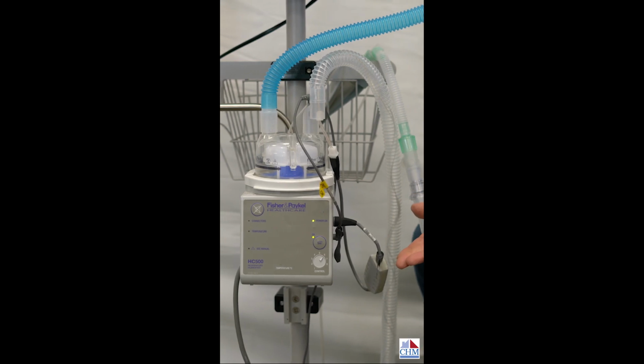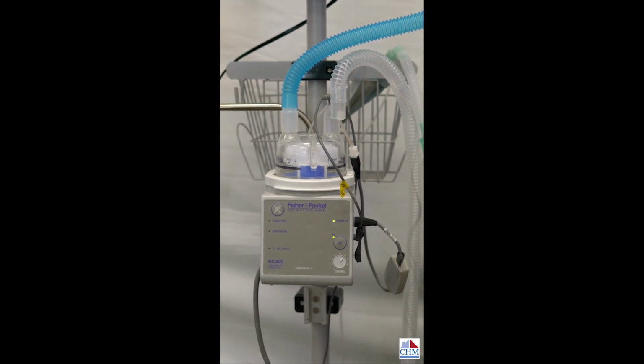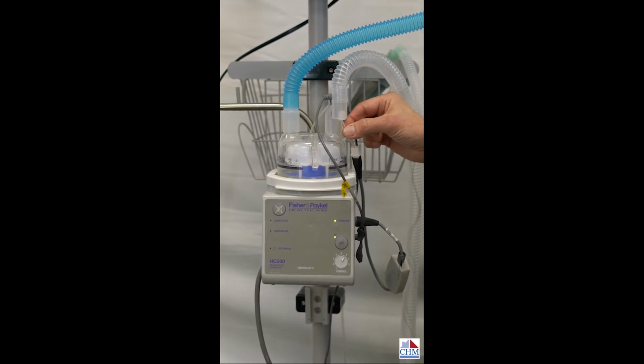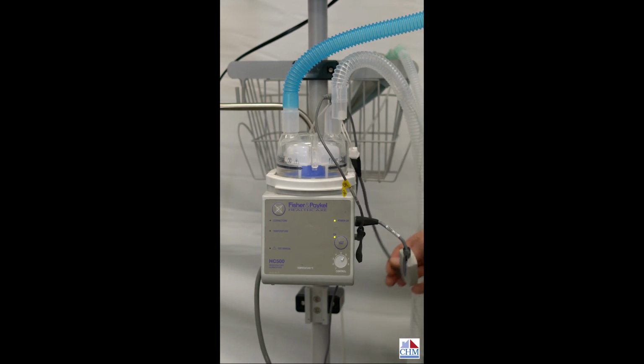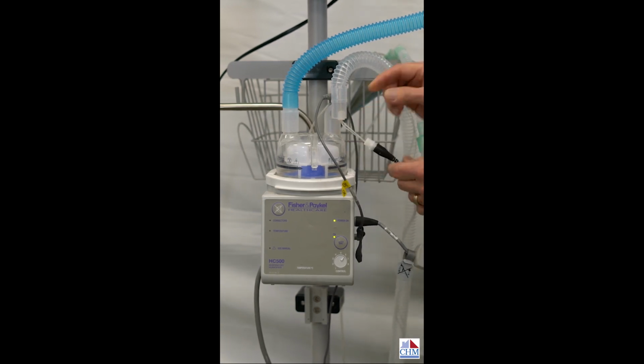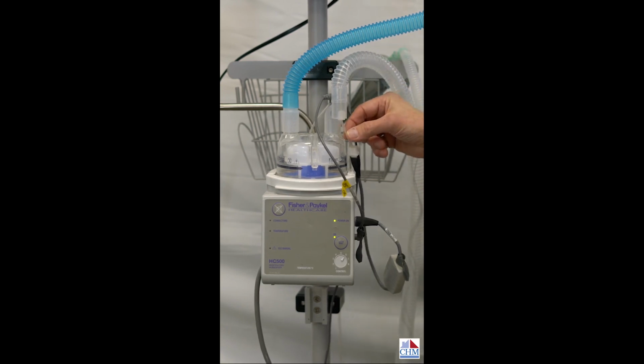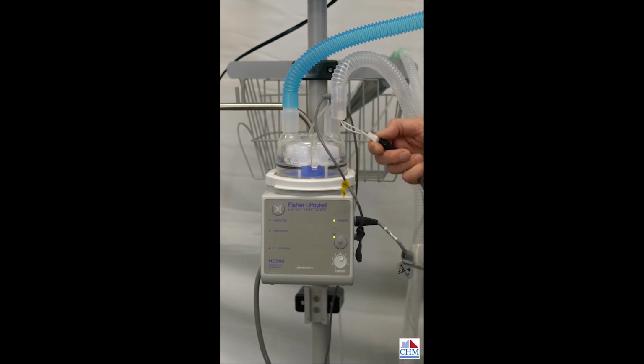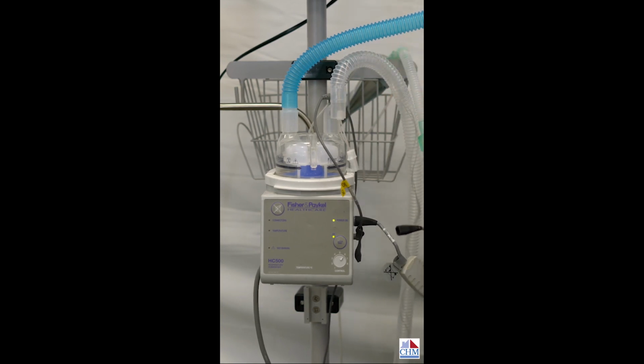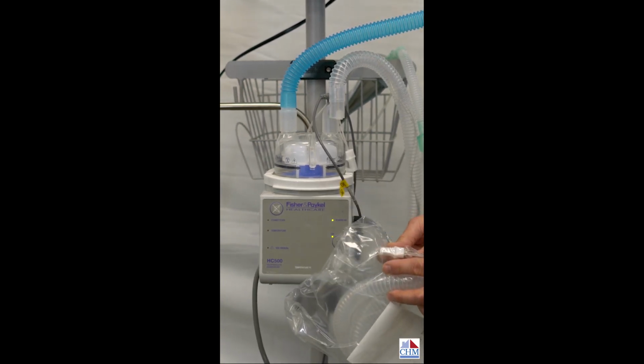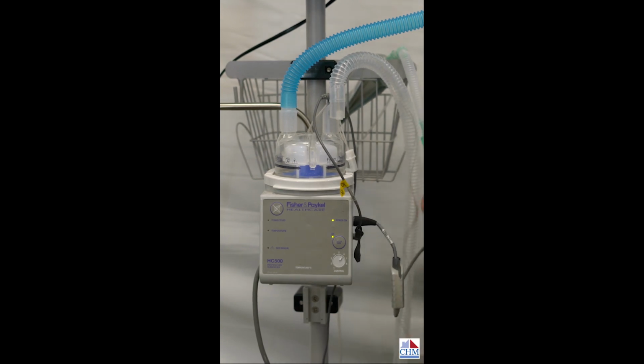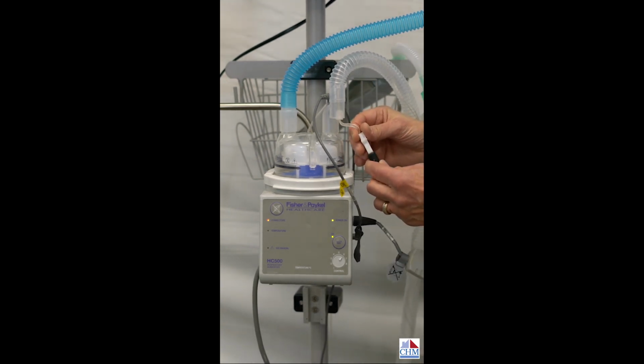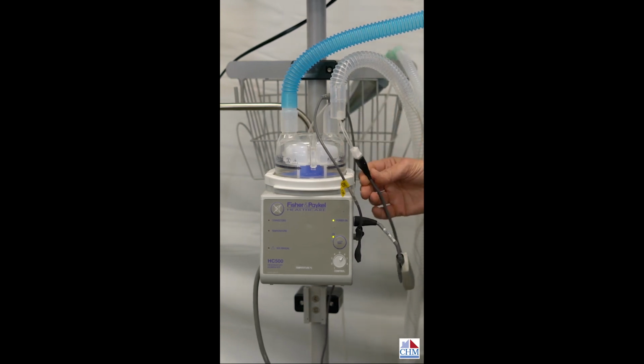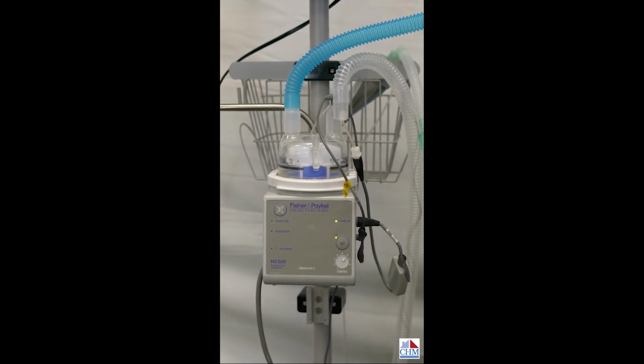So now, what do we do if we've exchanged that and it's still alarming? Connector. We've still got a connector alarm. That would be this wire. So remember, we've got the temperature probe, the heated wire adapter, but then there's also the wire that runs all the way through this circuit. So I've even seen brand new circuits where the wire was damaged and caused a problem. So again, rather than changing the entire circuit, just grab a new one and open it up enough so you can get that white connector out, and then just plug it in. Rather than changing the circuit first, just try plugging in the new one. And if that corrects the problem, then you know to go ahead and change the entire circuit.